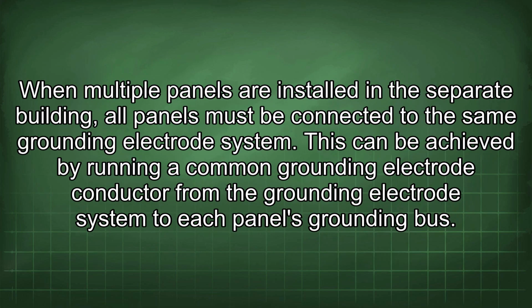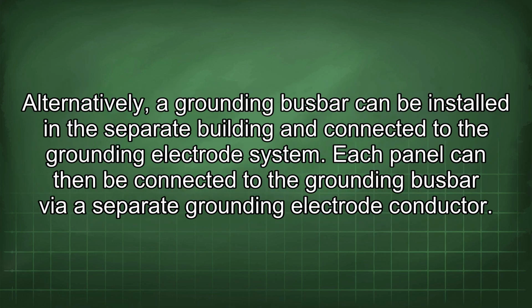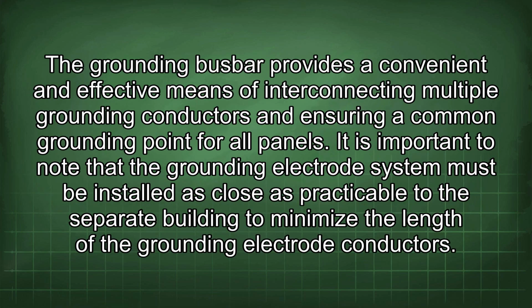When multiple panels are installed in a separate building, all panels must be connected to the same grounding electrode system. This can be achieved by running a common grounding electrode conductor from the grounding electrode system to each panel's grounding bus. Alternatively, a grounding busbar can be installed in the separate building and connected to the grounding electrode system. Each panel can then be connected to the grounding busbar via a separate grounding electrode conductor.